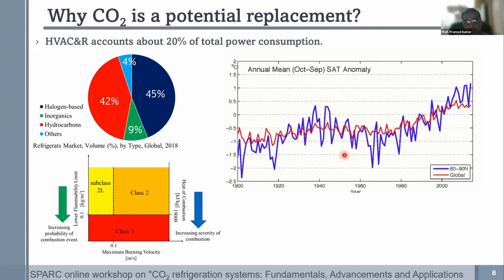So you don't really have to produce natural refrigerants. Like carbon dioxide occurs naturally. So essentially, by reducing the production of synthetic refrigerants, you're contributing significantly to reducing global warming potential, which Professor Hafner mentioned. The definition of ODP and GWP also needs to account for the amount of emissions that are emitted during the production of these refrigerants.